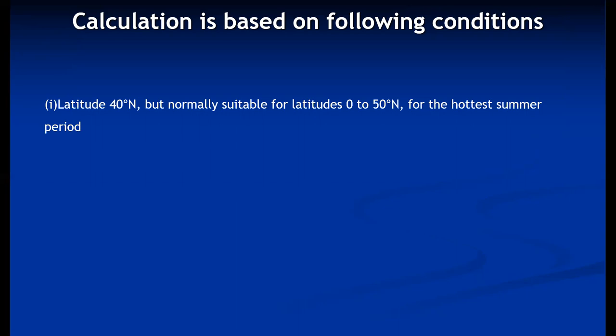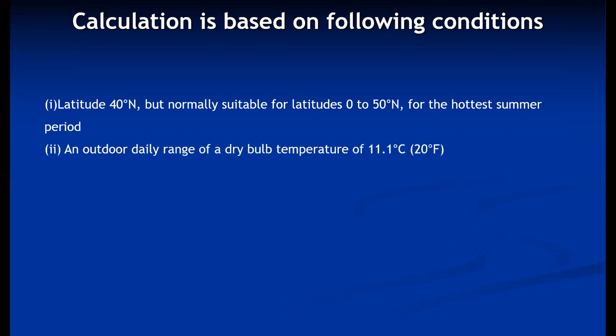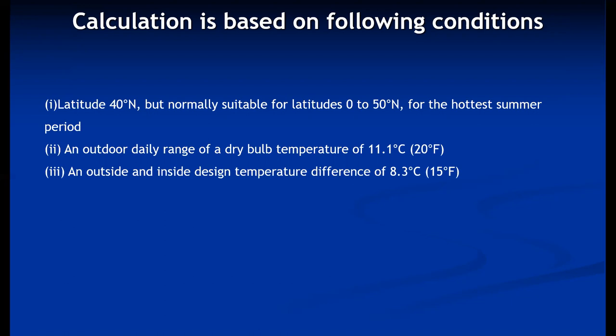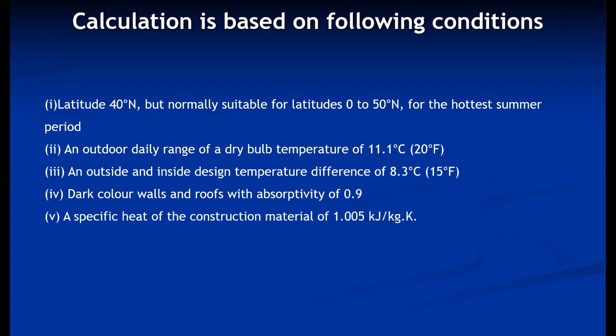The standard conditions used for calculating CLTD table values are: latitude of 40° N, suitable for latitudes 0° to 50° N; hottest summer period; an outdoor daily range of dry bulb temperature of 11.1°C; an outside and inside design temperature difference of 8.3°C; dark-colored walls and roofs with absorptivity of 0.9; and a specific heat of construction material of 1.005 kJ/kg·K.